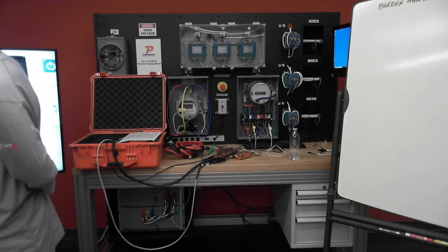B phase, I have a fail. What's the problem here? I come over here and it's my ratio. My ratio error is way, way, way, way high, right? I go from 0.32 on A phase and I'm 10.18% out on B phase. C phase tested just fine. So I'm not liking what I see.